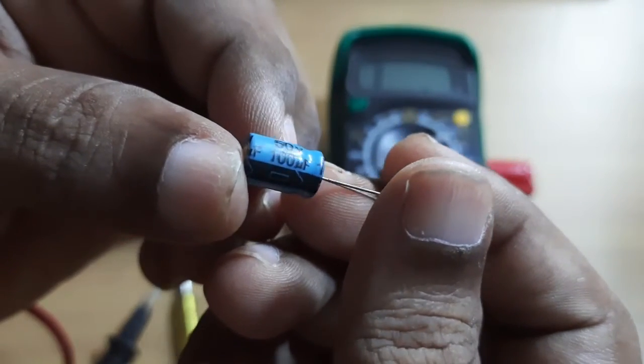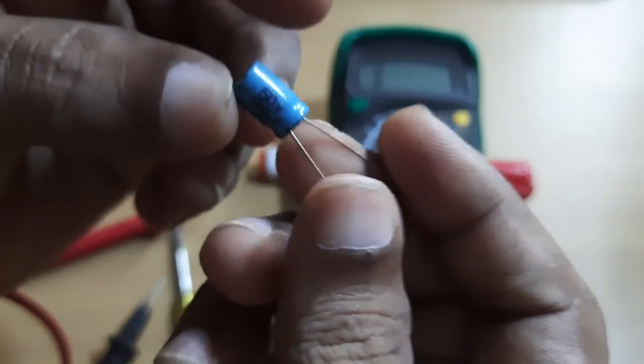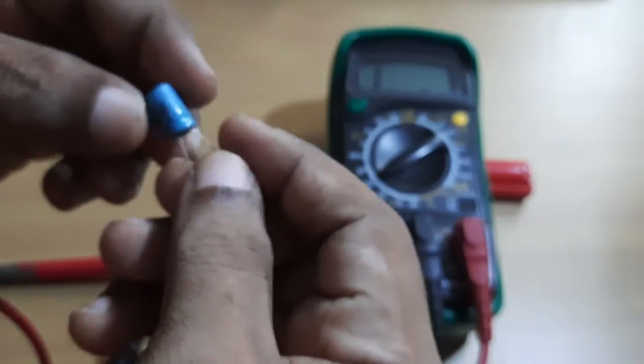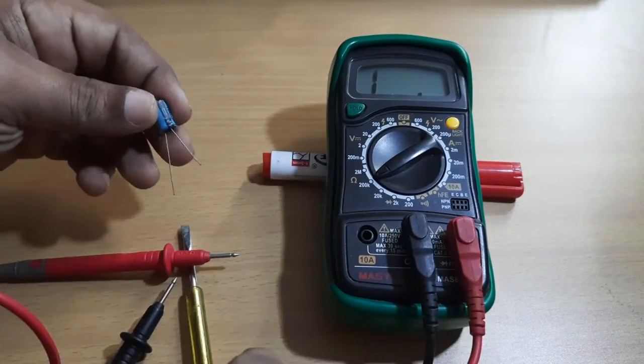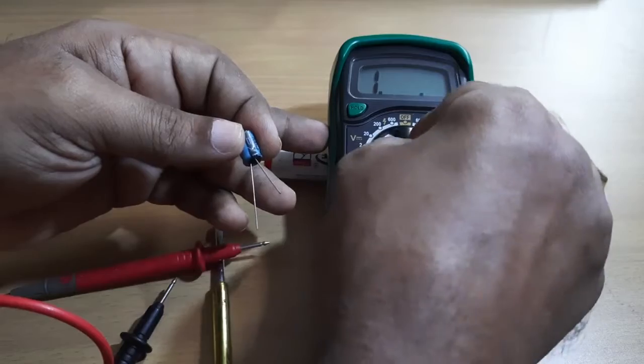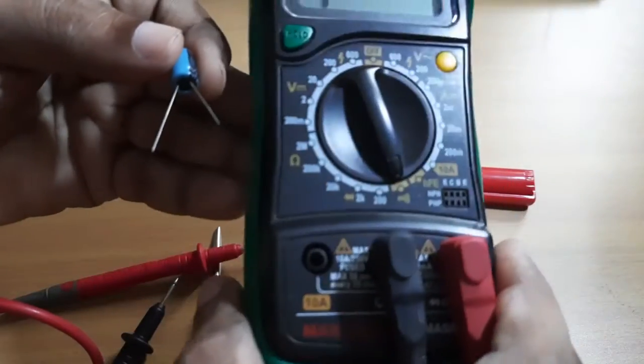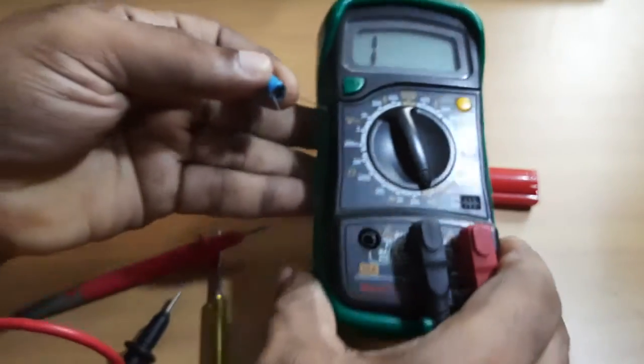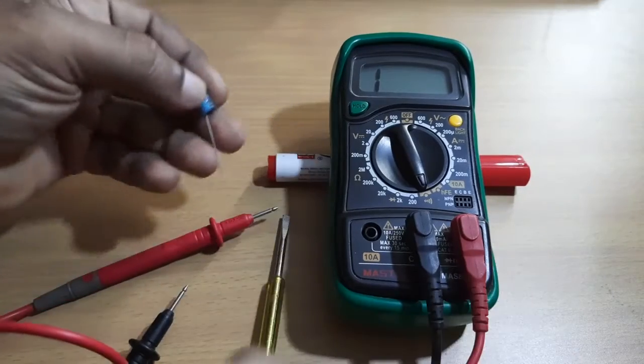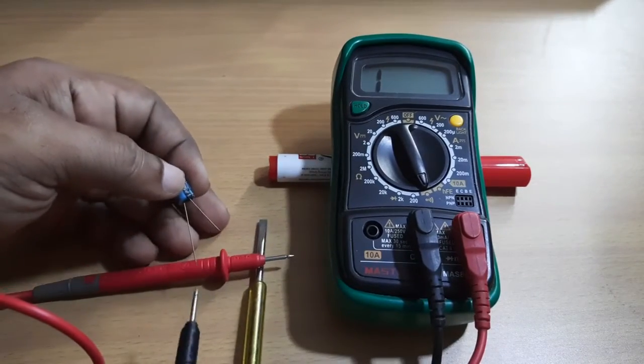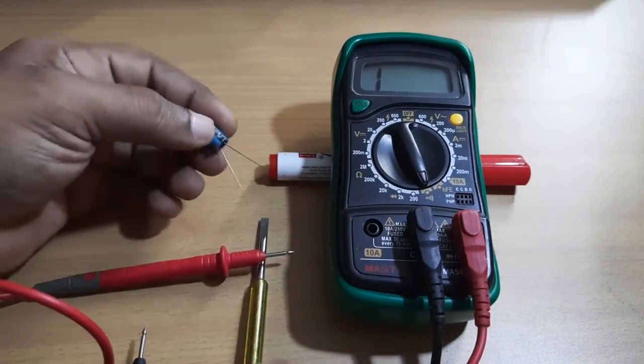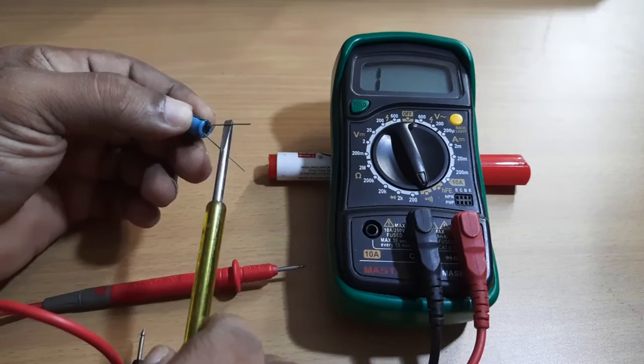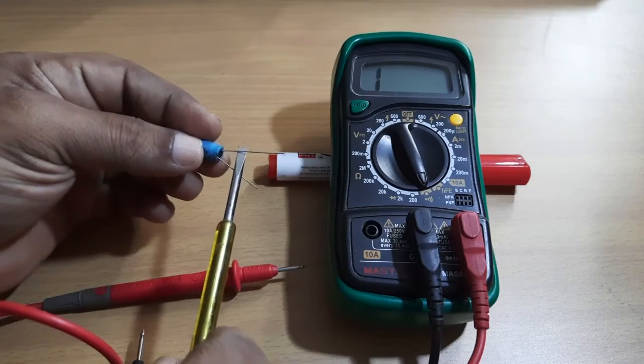4. The digital multimeter will show some momentary reading starting with a smaller value and briefly increasing in value. Then suddenly the reading stops and shows OL, open line or infinity. Note down the reading. 5. Disconnect the capacitor from the multimeter and repeat the steps from 1 to 3. If the reading remains the same, then it is a good capacitor.